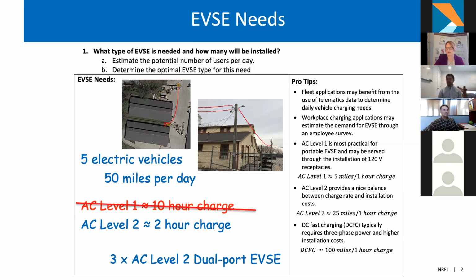Jesse, maybe go on to the next part of the worksheet. Sure, just one or two more comments. A lot of people feel tempted to install the highest power DC fast charging stations because of that tempting 100 miles per hour of charge. But there are much more drastic considerations required for DC fast charging with higher power requirements, like potential impacts on the utility. That's where utility coordination comes into play, maybe upgrades in their system as well as yours, and it's usually more than you'd typically require.